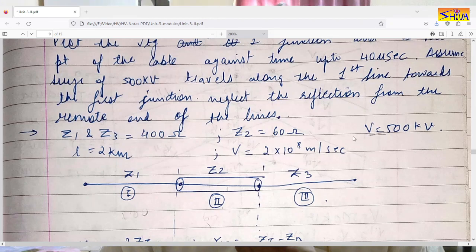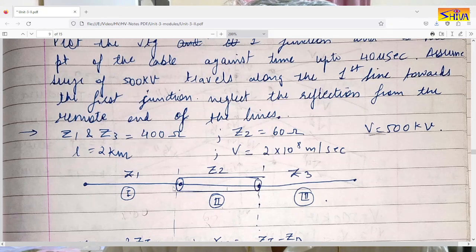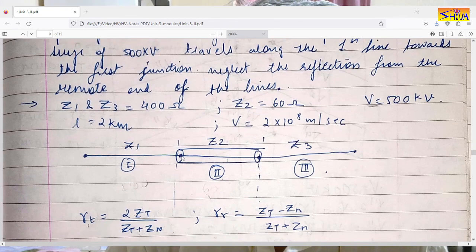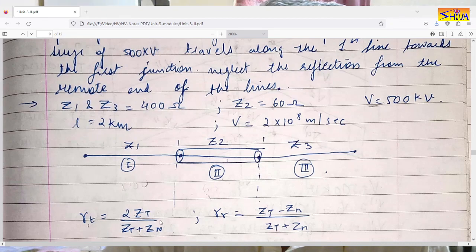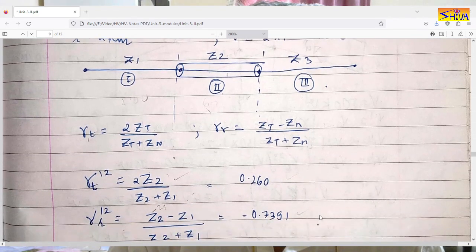The voltage entering the first junction from the first line is 500 kV. In the first part we have to compute the transmission and reflection coefficient at both junctions. The equation for transmission coefficient is 2×Zt divided by (Zt + Zn), and the reflection coefficient gamma_r is (Zt − Zn) / (Zt + Zn). First we compute the transmission and reflection coefficient at the first junction.